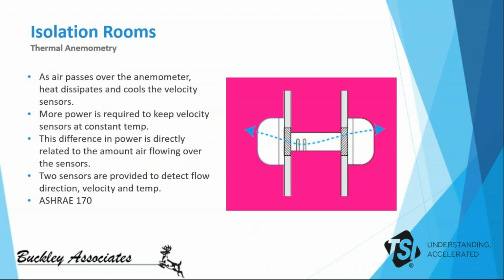So really quick, the way that TSI measures their pressure is via a thermal anemometer. I'm sure many of you are familiar with this technology, but for those of you who aren't, basically there's a sensor that generates a certain amount of heat, and it does its best to maintain that temperature inside a tube. But as air passes over that sensor, it's going to carry away some of the heat in a certain direction. So the amount of energy that it takes for that sensor to maintain a certain temperature is then equated to an airflow through the tube, and the direction of that airflow is determined by a second sensor that can either sense the lost heat or doesn't sense lost heat. So now we're going to determine which way the air is going. With both of these inputs, the sensor is then able to determine the pressure in relation to an adjacent room.